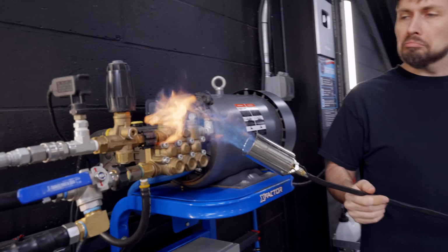So the other thing you would want to look at if the issue is that your machine is not starting, if it's not the pressure switches, it could be that time delay relay, that black box that we put the wires onto. That has been a failure point before. You can always take an electrical meter and make sure that you are getting 24 volts out of this transformer here, and that you are getting your 220 coming in the first place, obviously.